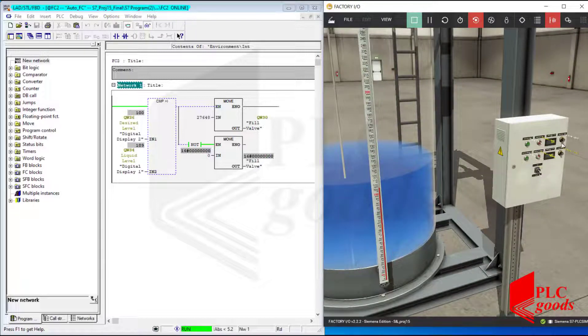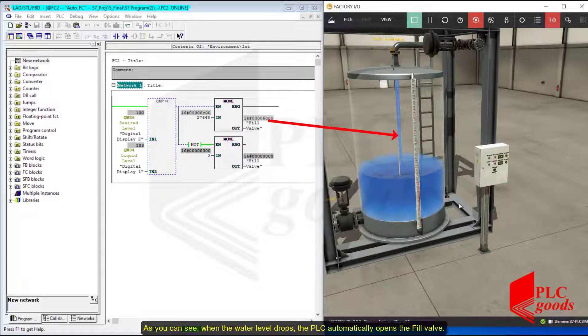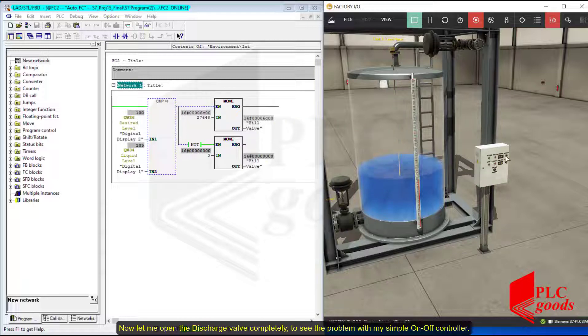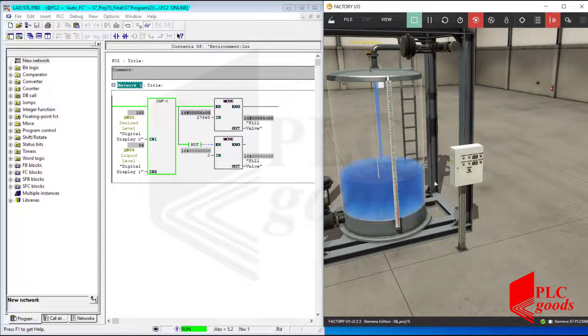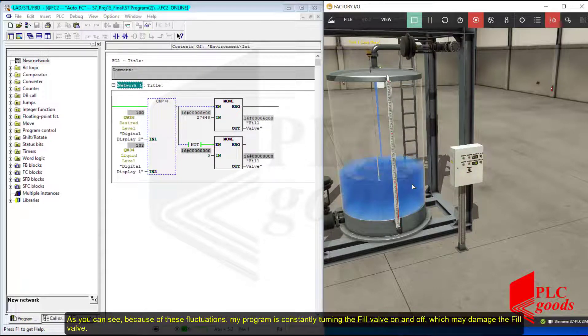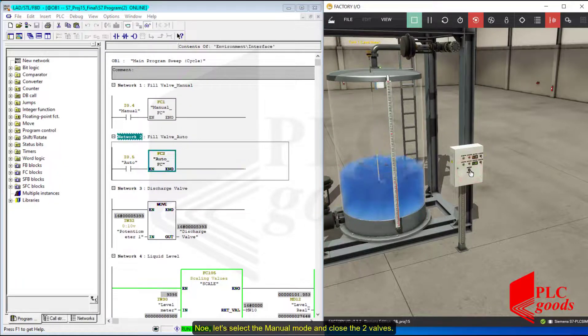Let's test it again when the discharge valve is open a little. As you can see, when the water level drops, the PLC automatically opens the fill valve. Now let me open the discharge valve completely to see the problem with my simple on-off controller. Because of these fluctuations, my program is constantly turning the fill valve on and off, which may damage the fill valve.